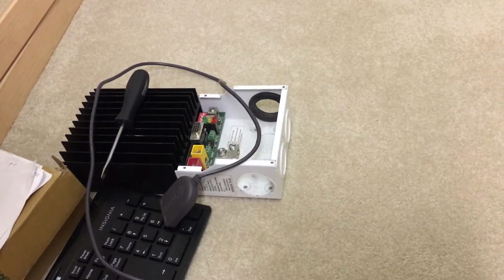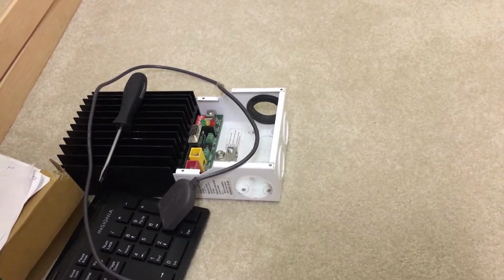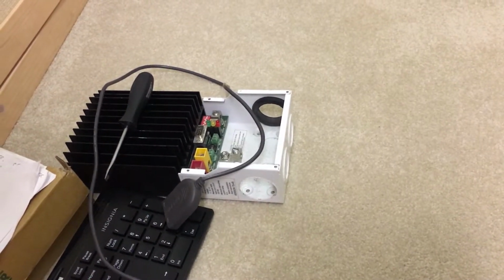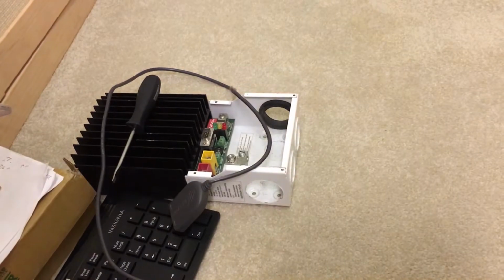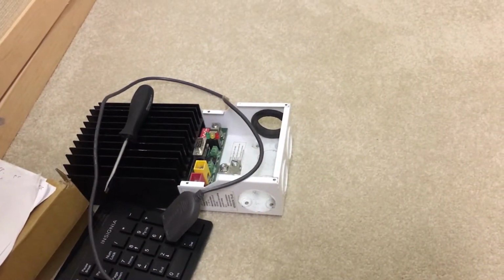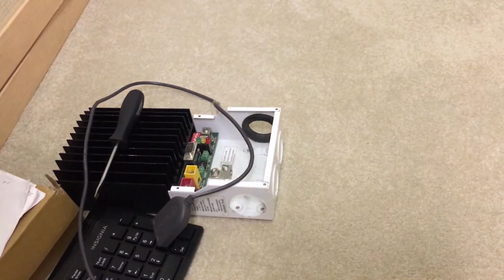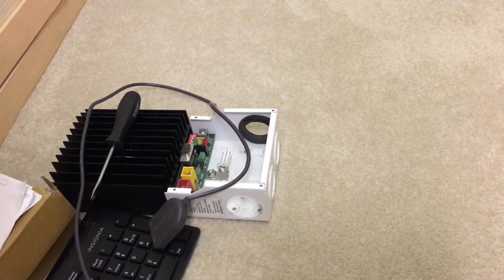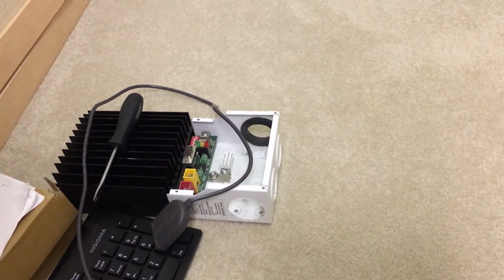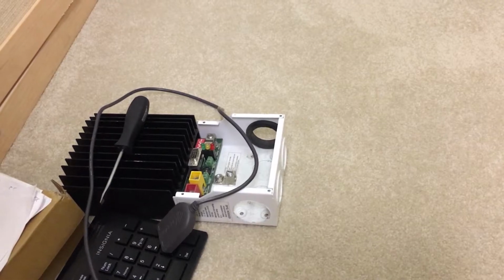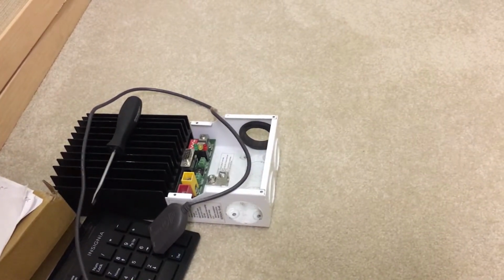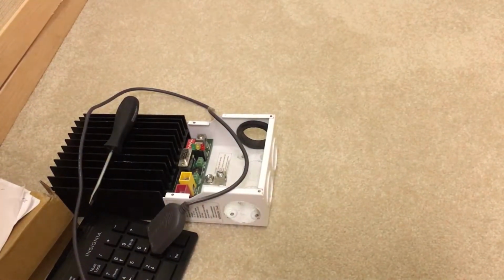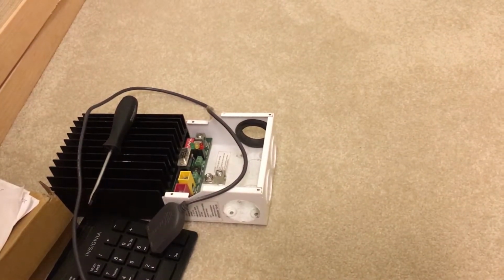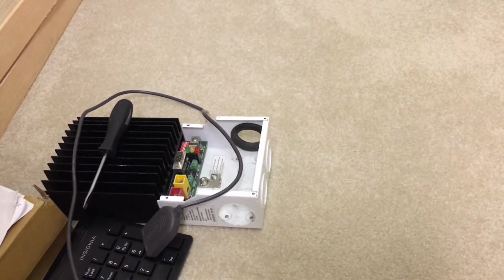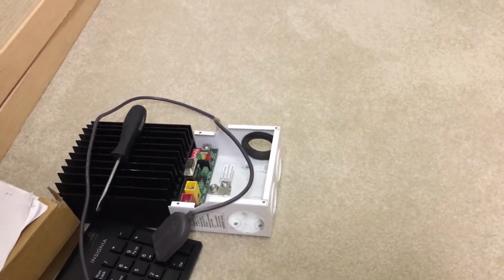So you got bulk, or in the MPPT case, it's just called MPPT. Then it gets absorption, and then there's something called equalize, which we don't really use for lithium-ion batteries. That's mostly used for lead acid and some other battery types. Then you have the float stage, and again, I'm not using that either. So we're really just using bulk and absorption for these lithium ions.